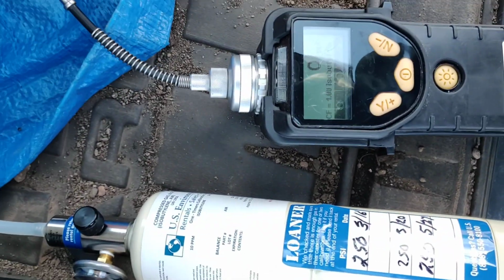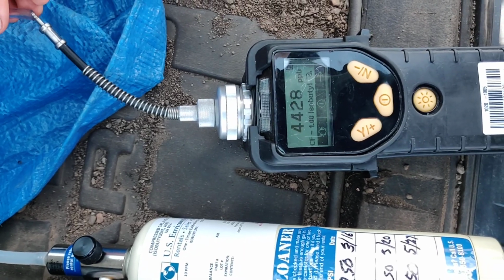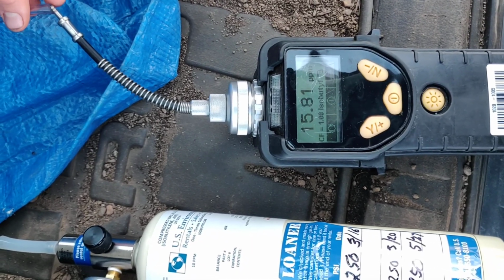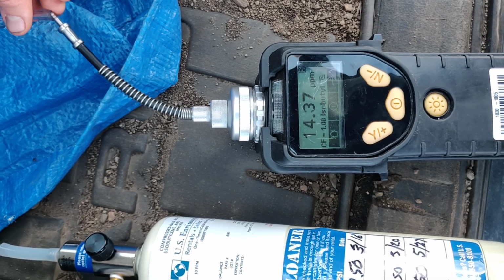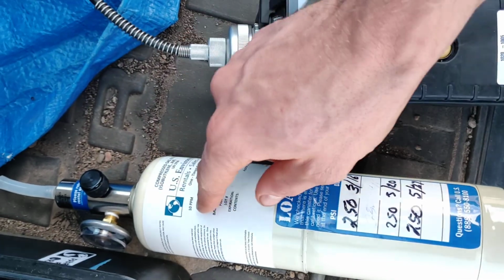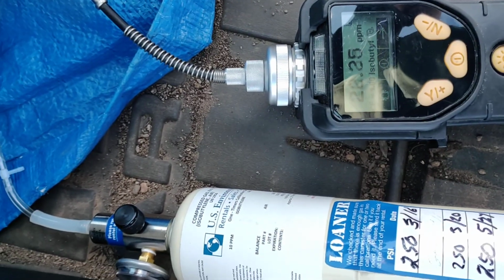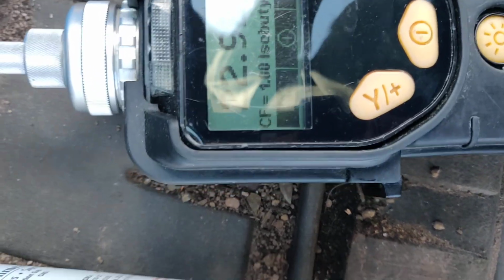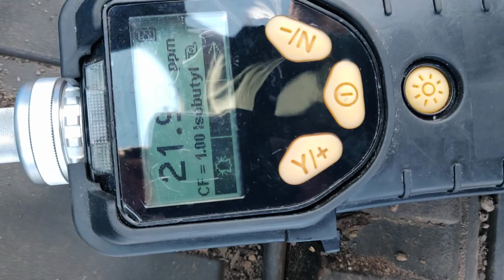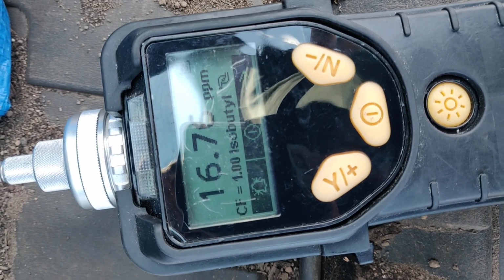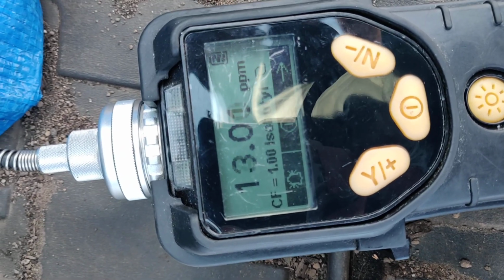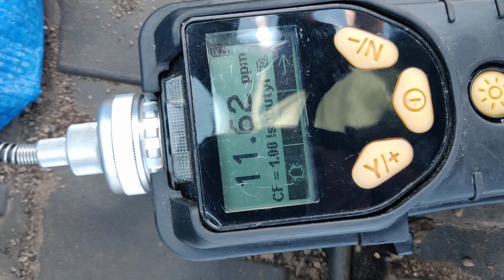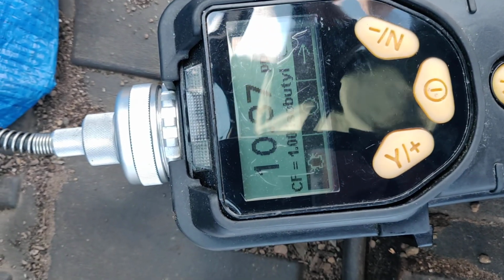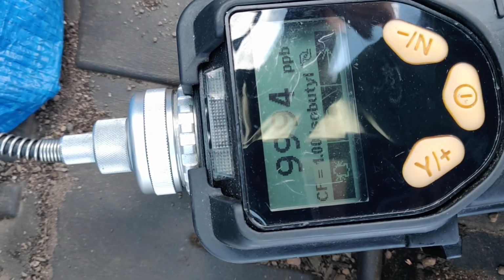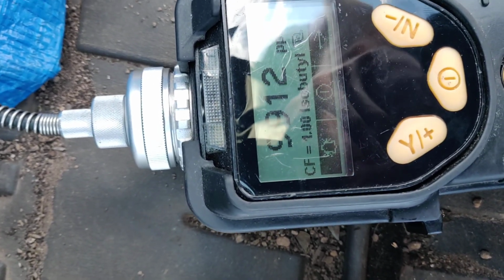Cut on my gas, not even directly connected, but it pumps the air into it. And this is typical, actually, when I do this. This is called a bump test. You hook it up to a known concentration, and you look to see if it's going to read that concentration correctly. I'm pretty concerned because I'm getting a very different reading than what I measured it to. But look, see, it's dropping down, stabilizes. When the reading is stable, that's your bump. That's pretty good.